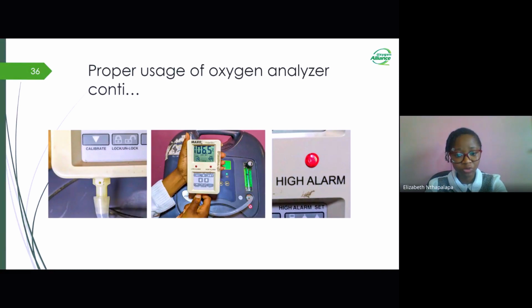going above our threshold of 99%. It has reached up to 106.5%. This is because we blocked the hose which acts as the outlet, and this leads to our oxygen analyzers displaying a high alarm alert. Also, another thing that we need to be conscious of not doing will be explained in the next slide, please.